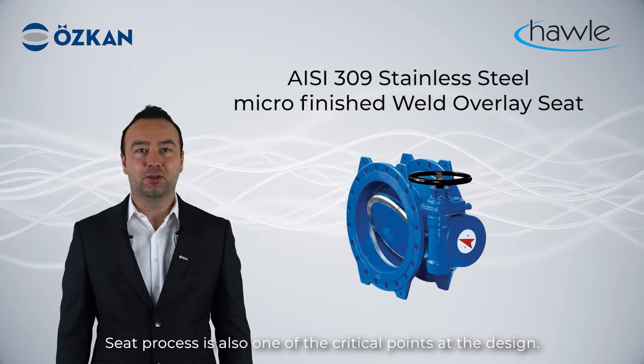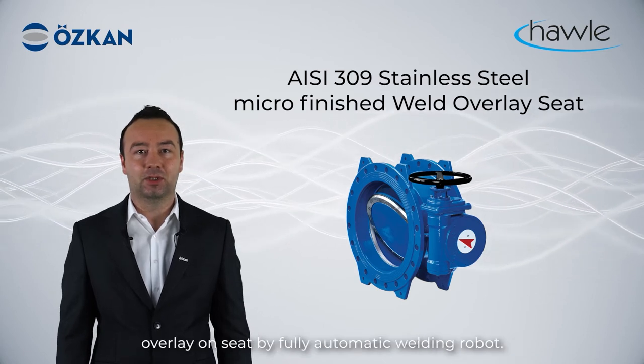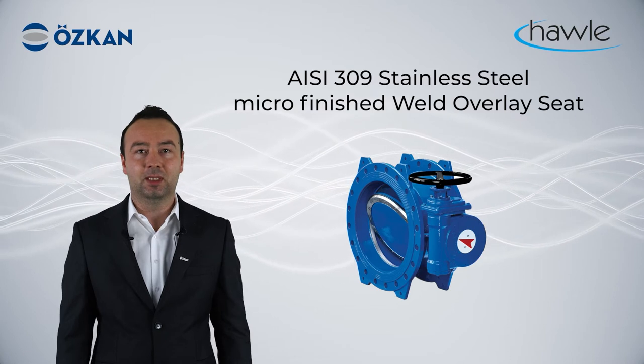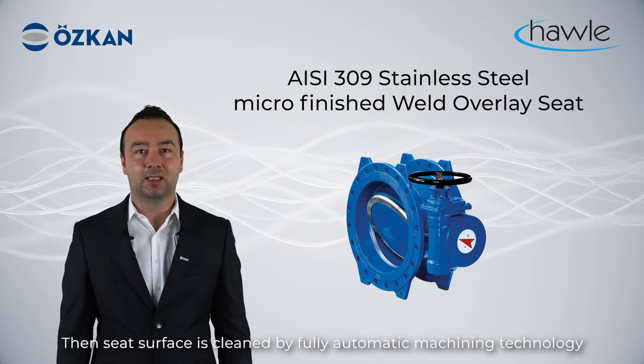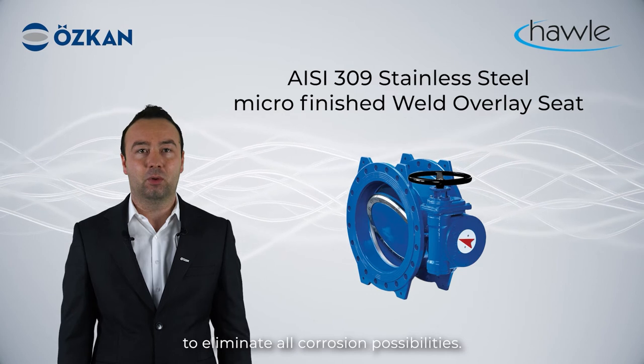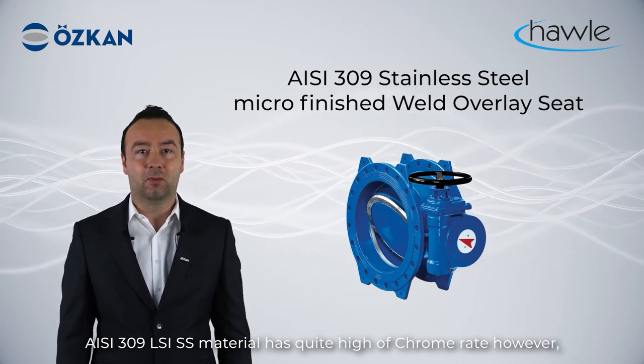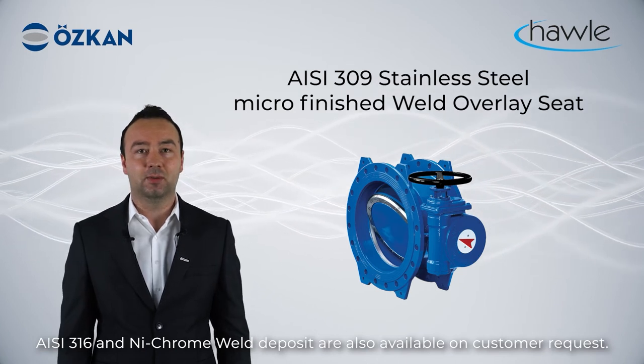The seat process is also one of the critical points in the design. Özkan Hawle applies a stainless steel microfinish weld overlay on the seat using a fully automatic welding robot. This non-replaceable seat technology ensures a superior and robust seating surface. The body is fully coated by fusion bonded epoxy, then welding is applied on the seat area. The seat surface is then cleaned by fully automatic machining technology to eliminate all corrosion possibilities. AISI 309L stainless steel material has a quite high chrome content; however, AISI 316 and nickel-chrome weld deposit are also available on customer request.